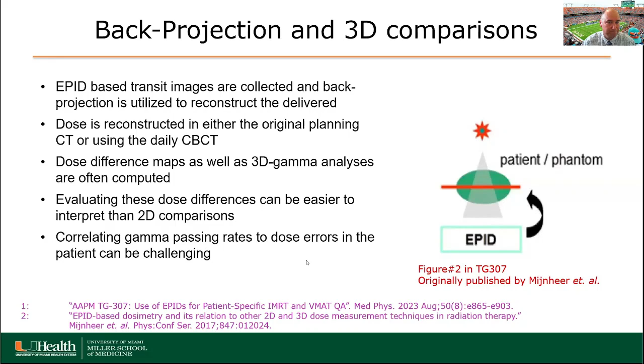Again, these dose differences are easier to evaluate than two-dimensional comparisons. But again, correlating gamma passing rates or failure rates to specific dose errors can be challenging. And again, 3D dose calculations using EPIDs and transit dosimetry suffer from some uncertainty due to a lot of the assumptions that have to be made to make that measurement calculation.